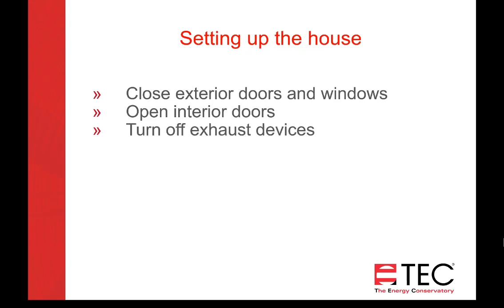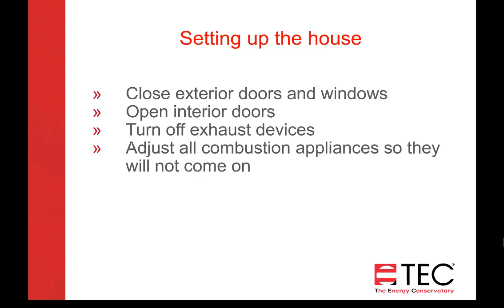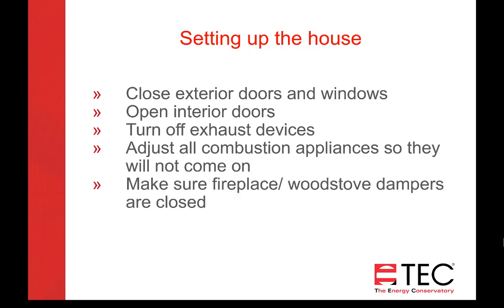And open all interior doors. Turn off any devices that will change the pressure in the house. Anything capable of changing the pressure in the house, make sure that's turned off. All combustion appliances need to be adjusted so they will not come on during the test because you are going to be pulling air down any chimneys. If they're natural draft appliances or induced draft, you'll be pulling air down chimneys during the test, so you want to make sure those appliances don't come on. Make sure there's no fire in wood stoves or fireplaces. Make sure you let your customers know that ahead of time and make sure the dampers are closed. If you leave a fireplace damper open and there's ashes in the fireplace, you won't do that a second time.